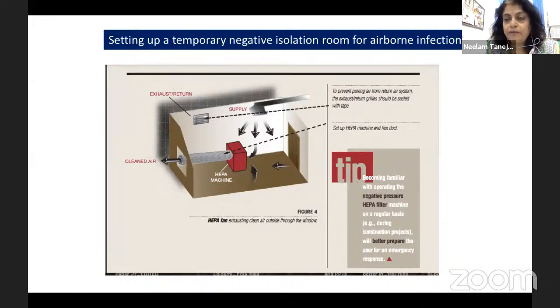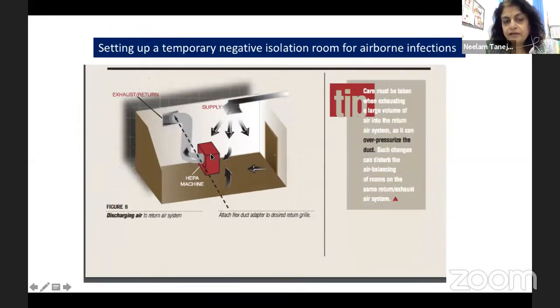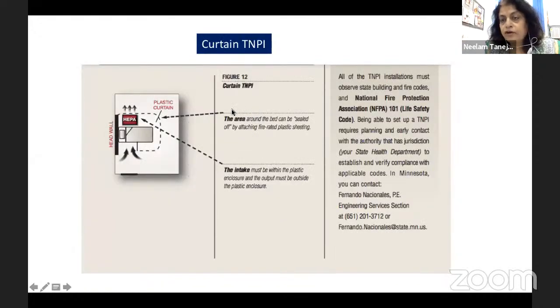Now, the COVID pandemic taught us a lot. Every hospital was short of these negative pressure isolation rooms. So we could create a temporary negative isolation room for these airborne infections by simply putting a portable HEPA machine here, closing or sealing off the exhaust or return air, and attaching the HEPA filter with a flexible tube duct which opens outside through a window, and there is an adapter here. Another type is having this portable HEPA filter machine and this flexible duct open into an exhaust return. But you have to take care: if there is more than one exhaust return, then you have to seal those.